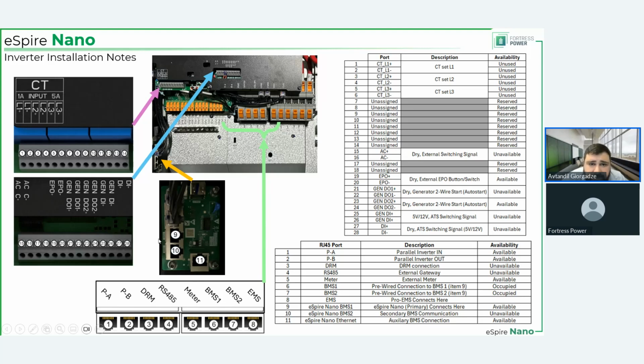Then on the inverter, you have PA and PB ports. This is for parallel inverter communication. So starting with PB, you go to the PA of the second inverter. From the second inverter's PB, you go to the PA of the third inverter, and so forth, all the way to number 6. Also, it's not shown here, but there are dip switches here, 2 of them. For the first inverter in the chain and the last inverter in the chain, those must be on, all the others should be off. If it's one inverter, that one is the first one or the last one, depends on how you look at it, so obviously, it will be on. If you have 2 inverters, the first one is the first one, the second one is the last one, so both of them on. If you have 3 or more, first and last on, the middle one's off.